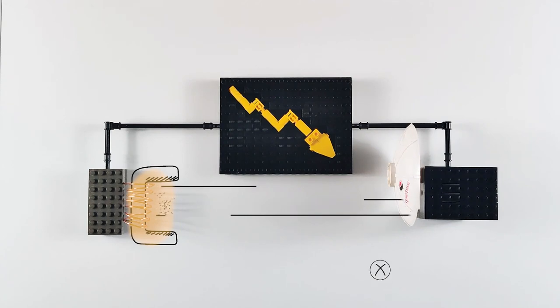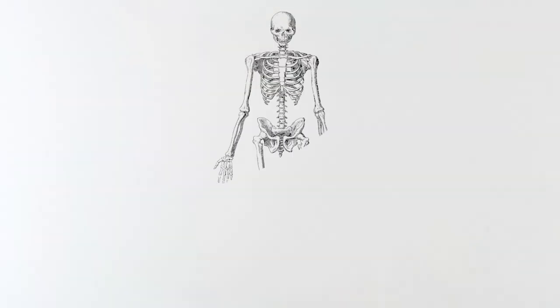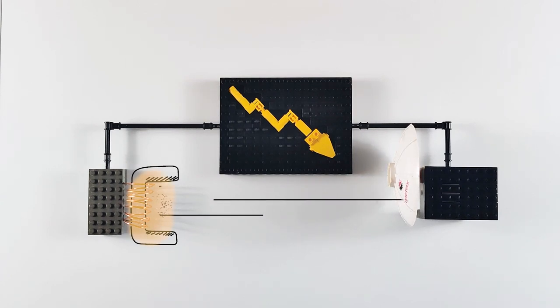Of course both types of anode are used in medicine nowadays. The fixed anode is used for example in examining teeth, hands or feet. The rotating anode is used for imaging bigger and thicker structures, for example the chest or the spine. Although we've mentioned most elements of the x-ray tube, there are also few others necessary for its work.